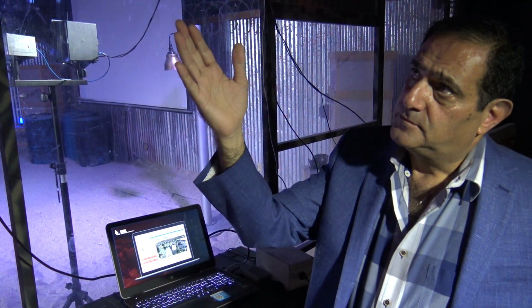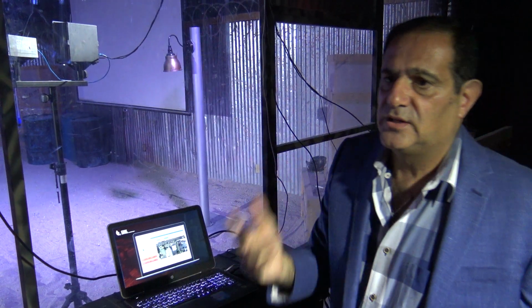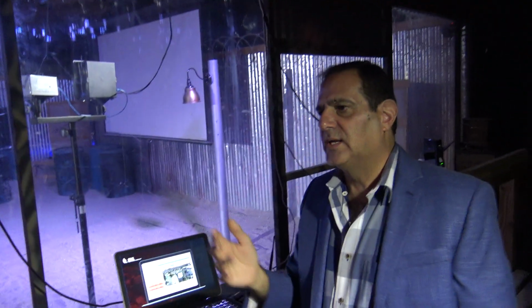The sensor itself also wakes up once a day, does a self-test, and sends a heartbeat. I will show you this on the real system. The heartbeat tells the system that I'm here and I'm good to go, I'm alive. If the sensor does not send a heartbeat, you will get a text message on your phone telling you that this sensor at this location did not report in today. The sensor also has an accelerometer in it. So if somebody tries to mess with it, move it, or whatever, it will let you know that.